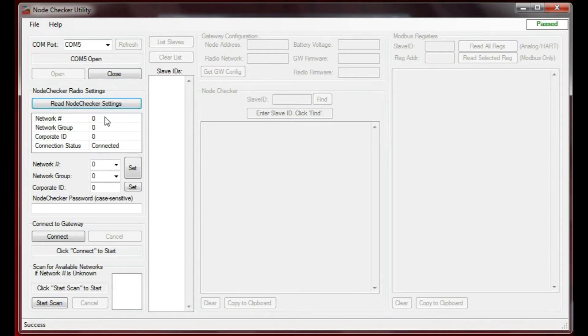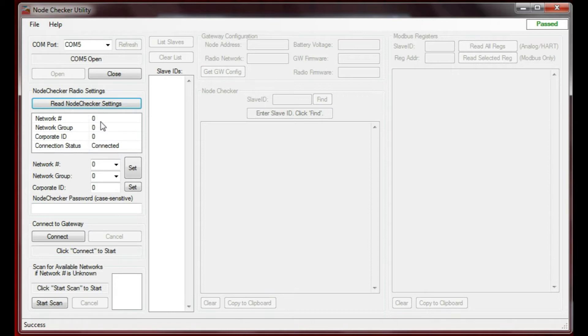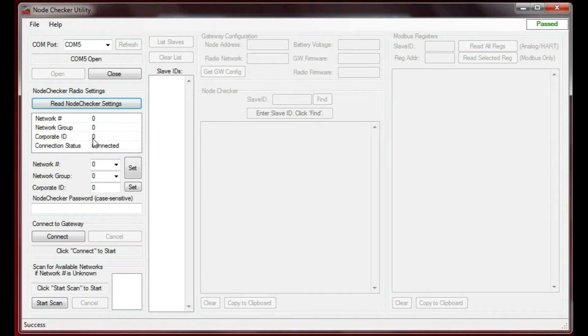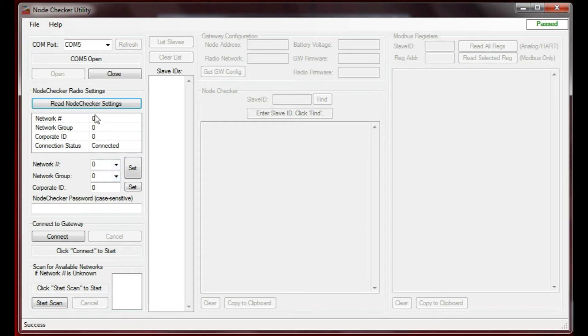What you need to do is set the network, the network group, and the corporate ID to be exactly the same as the system that you're trying to connect to. For the test system, I've set all of these to zero. They're set correctly here. If you needed to change them, you would change them right down here and press these Set buttons.